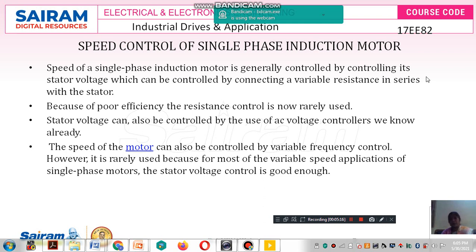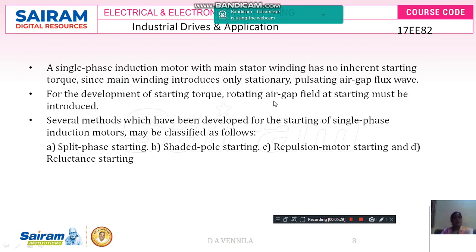We use only the stator voltage control method, specifically using an AC voltage controller. A single phase induction motor with only the main stator winding has no inherent starting capacity — it does not have inherent starting torque — since the main winding introduces only a stationary pulsating air gap flux. Therefore, the single phase induction motor is not a self-starting motor.